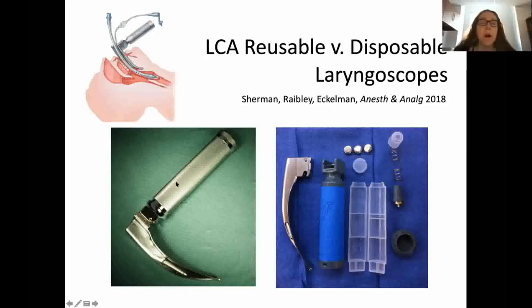The reason why is that the handle and the tongue blade are considered separate units. The tongue blade goes down to central sterilization supply for minimum high-level disinfection. The handle historically has been low-level disinfected in the operating room, and there's a loophole in the regulations about what level classification this handle should be.